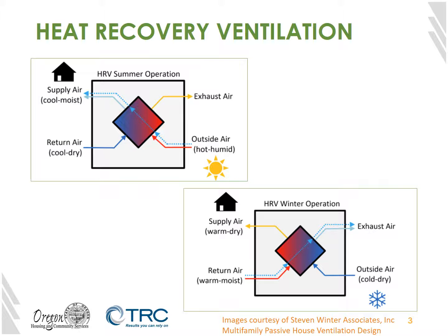An HRV in the winter allows heat to be transferred between the two airstreams at that recovery energy core I mentioned, but the moisture in the return air is not transferred to the supply air as it's exhausted from the building. And therefore, the moisture is actually able to be exhausted, and as a result, controlling the indoor relative humidity in the winter can be less challenging with the heat recovery ventilator. So overall, it's most definitely a pro for its use in the winter and for the majority of the summer, with only some real concern in the Northwest being for those spring or rare humid months.